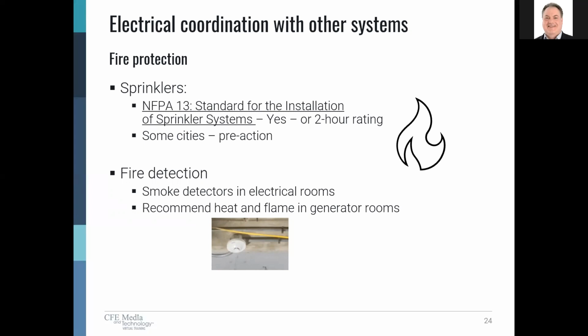Fire detection is always the way to go with electrical rooms. You want smoke detectors in electrical rooms. In generator rooms, obviously because of the airflow, you can't use smoke detectors, and you want to look at heat or flame detectors in generator rooms.